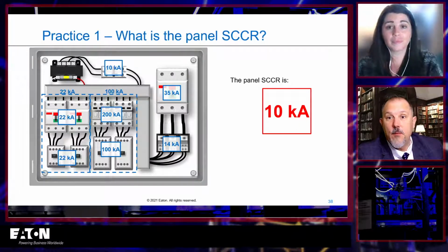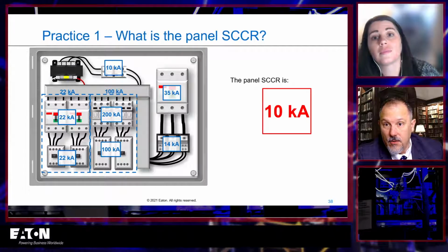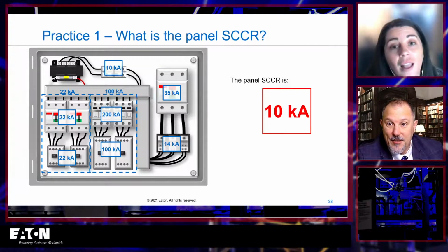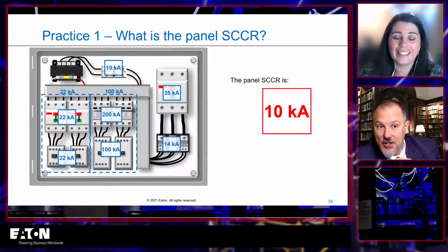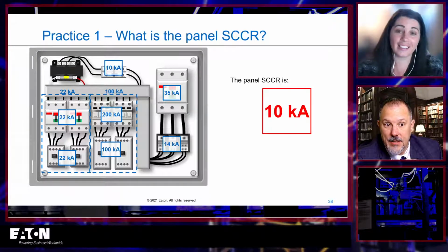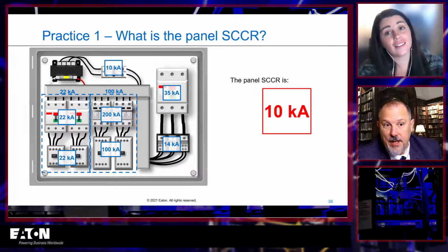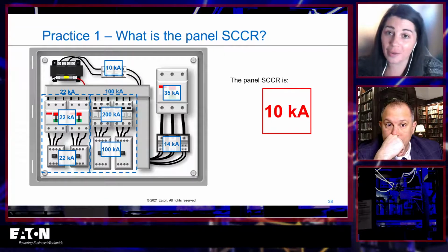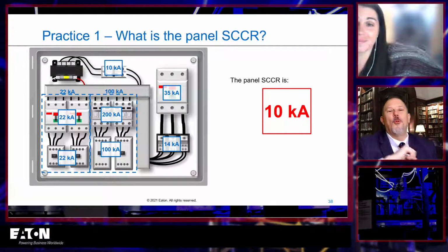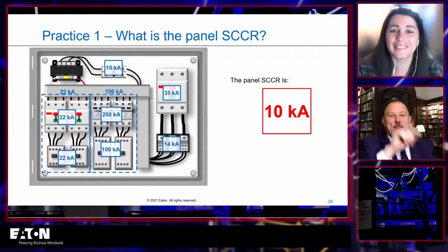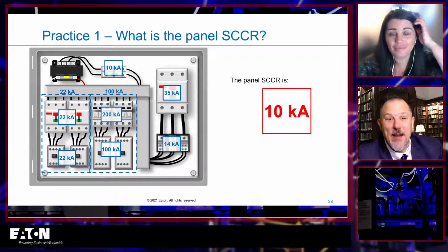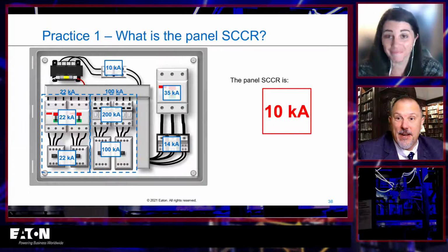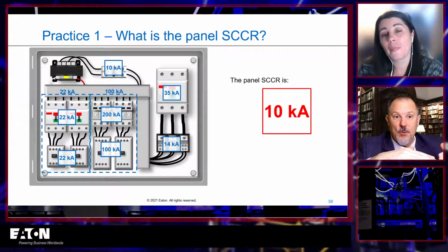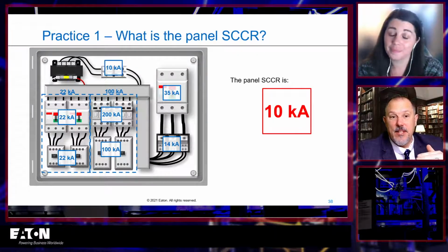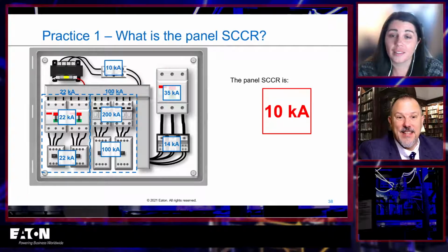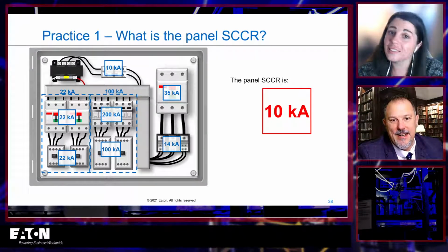And now, if I wanted to raise the SCCR of this panel, are you going to cover that? If I could address that breaker that's 10K, then I could at least pick it up to 22K, right? Oh, you're at 14 because of the power distribution block. Oh, yeah, that's right. I can see why this can be kind of fun trying to figure out how to get it up to the right SCCR number that you need, because like you say, I fixed the 10, but then I have a problem over there at the 14. Yeah, I've got to fix that.